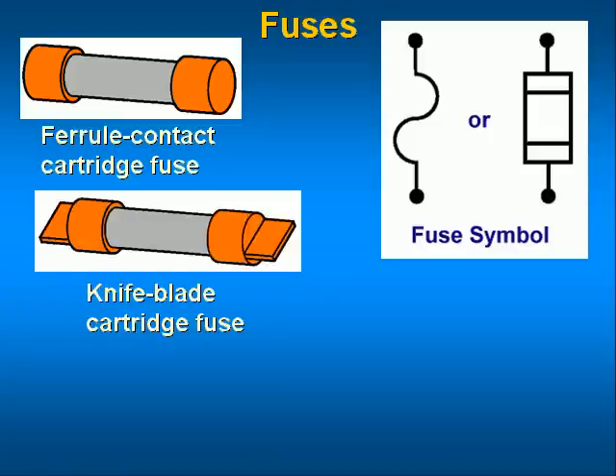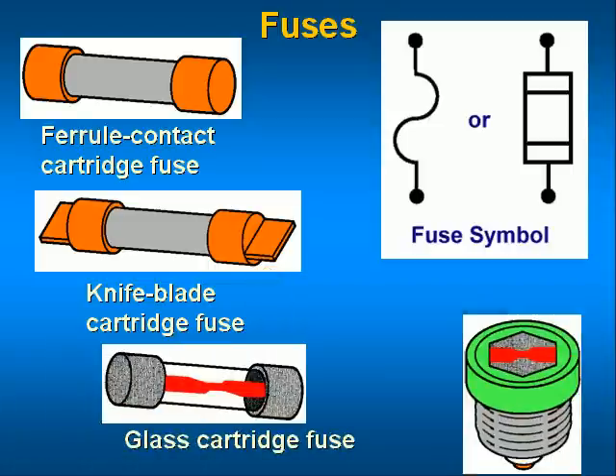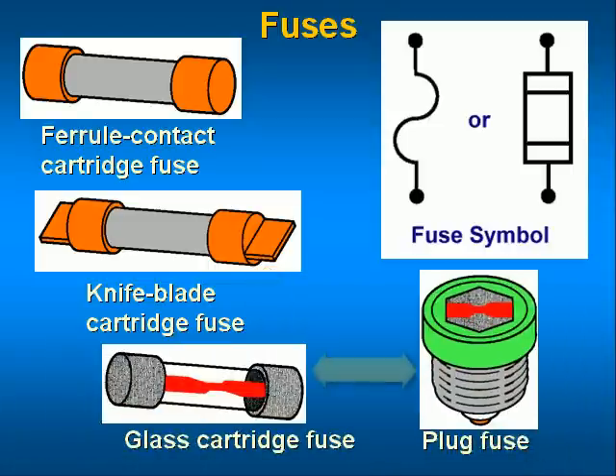There are some fuse types illustrated here. The knife blade connection is used to provide a larger surface area for the electrical connection, so larger current densities can be accommodated. The condition of the fusing element is visible in some fuses, so the fuse condition can be directly observed. Without this feature, measurements must be made.